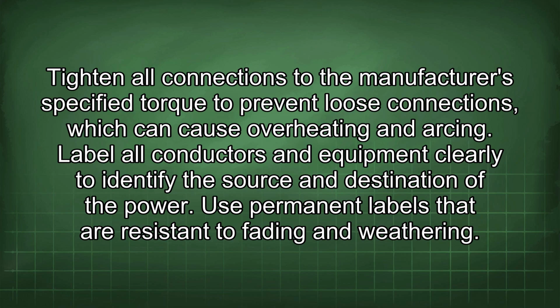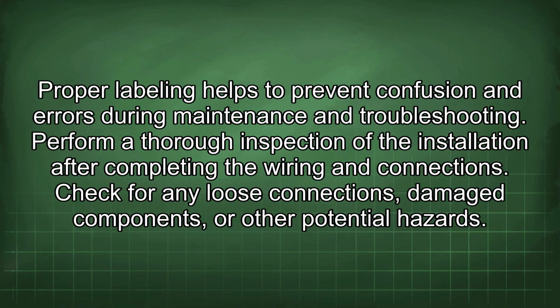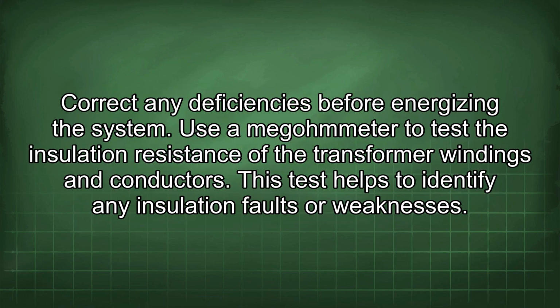Use permanent labels that are resistant to fading and weathering. Proper labeling helps to prevent confusion and errors during maintenance and troubleshooting. Perform a thorough inspection of the installation after completing the wiring and connection. Check for any loose connections, damaged components, or other potential hazards. Correct any deficiencies before energizing the system.